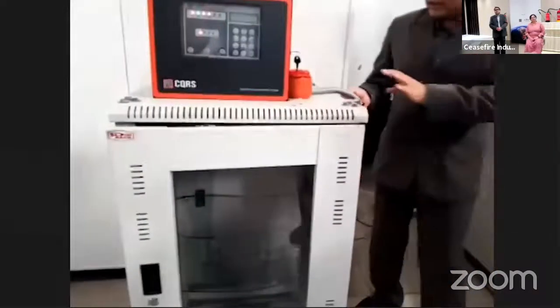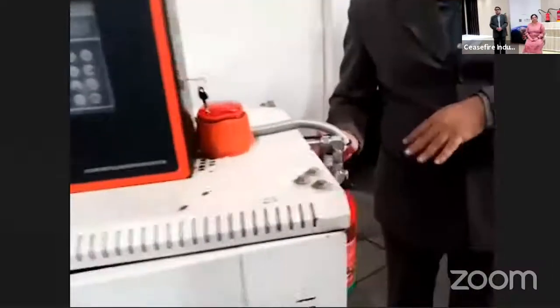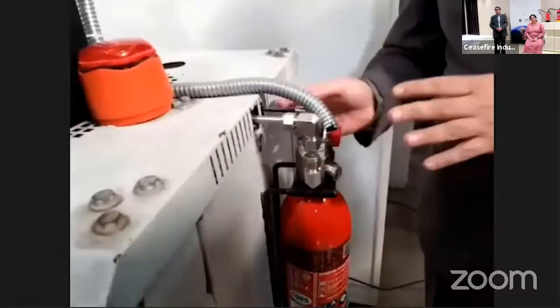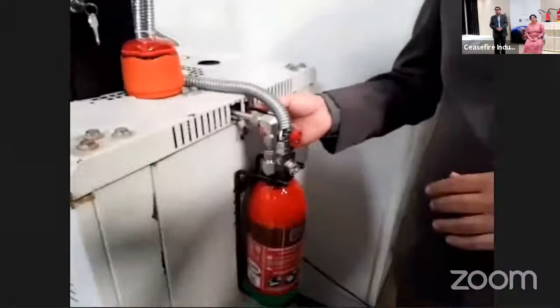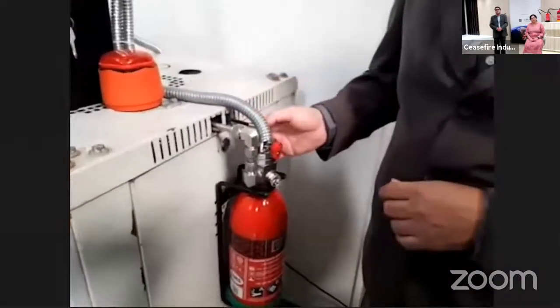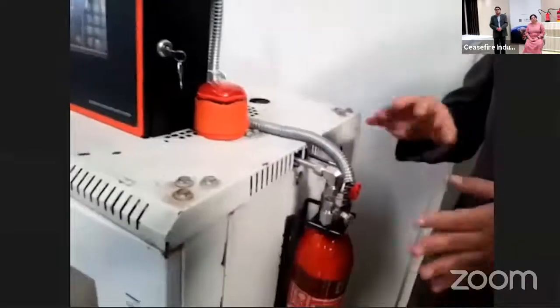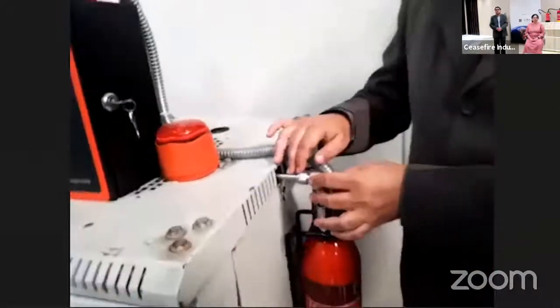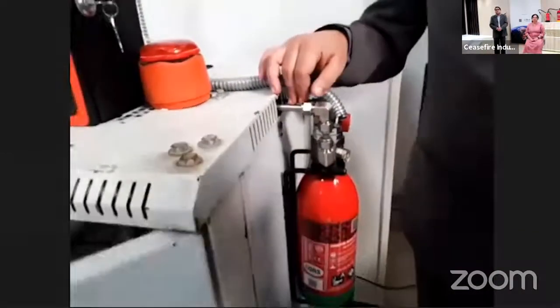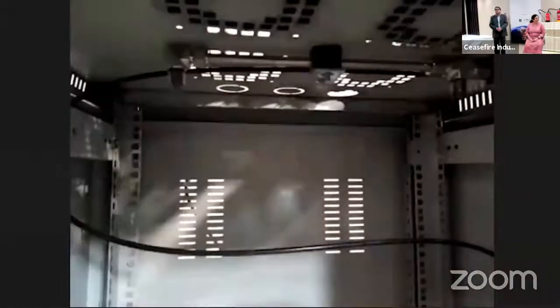In the indirect system, as I told you before, the heat sensing tube is connected to the head of the valve. The valve will be closed as long as the heat sensing tube is pressurized. We use dry nitrogen to do that. The expulsion of the gas would be through a separate line. If you look from inside, the tube is there to detect the fire, and there is a separate discharge pipeline and nozzles.